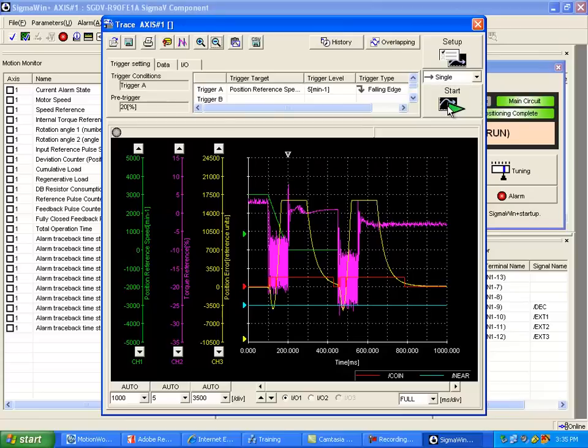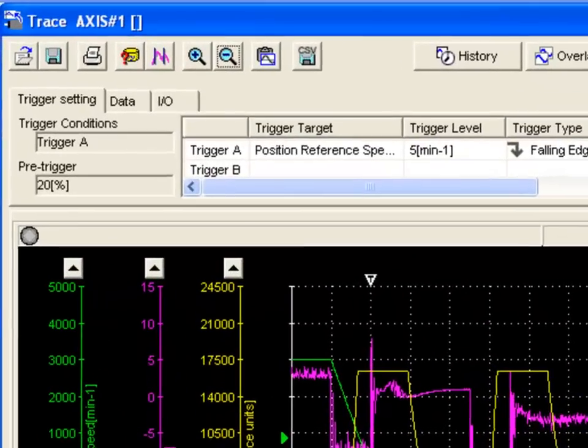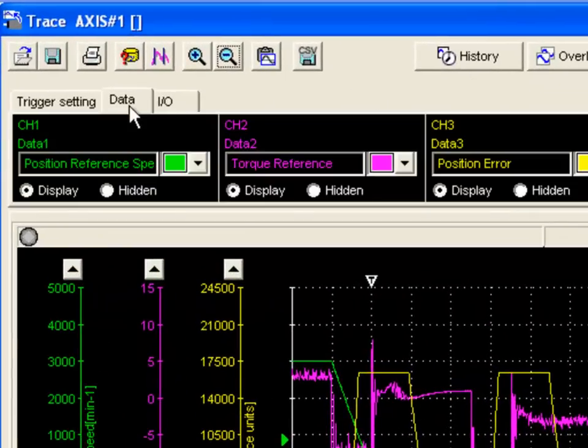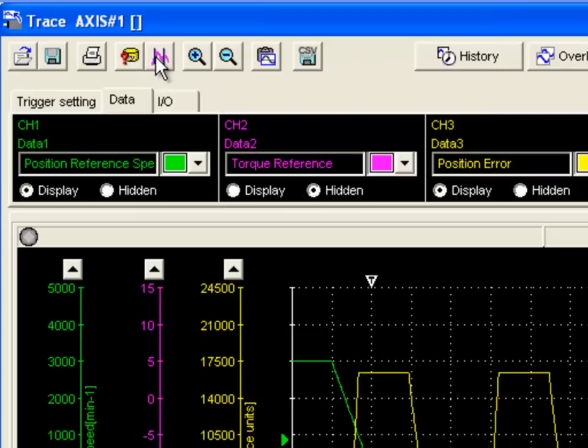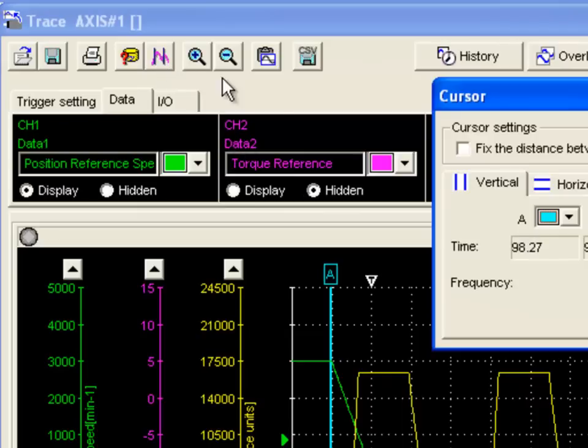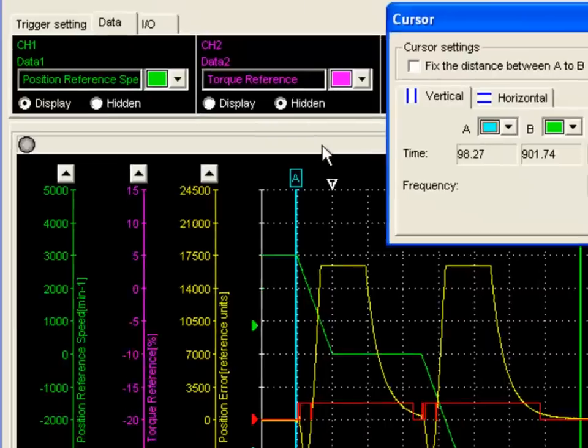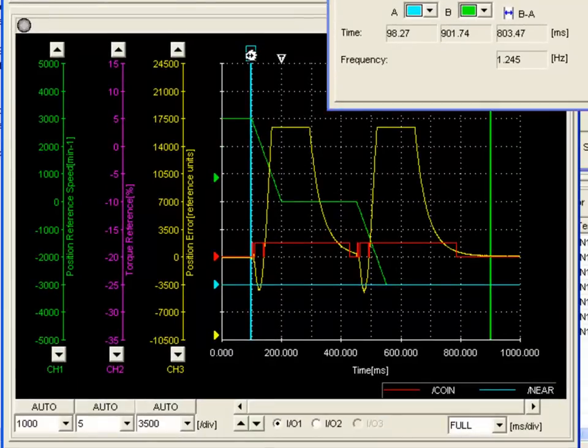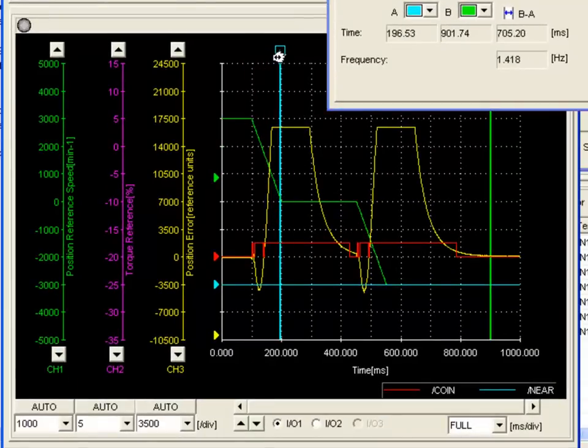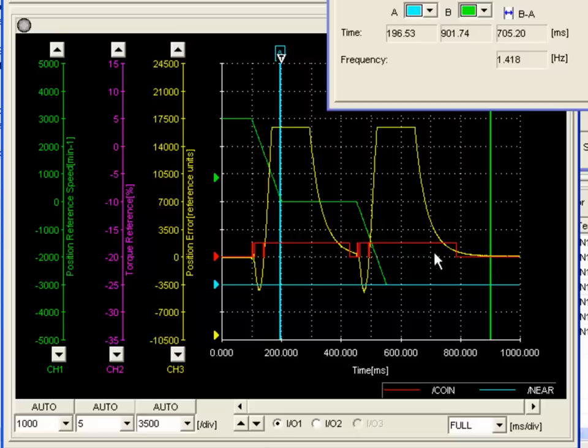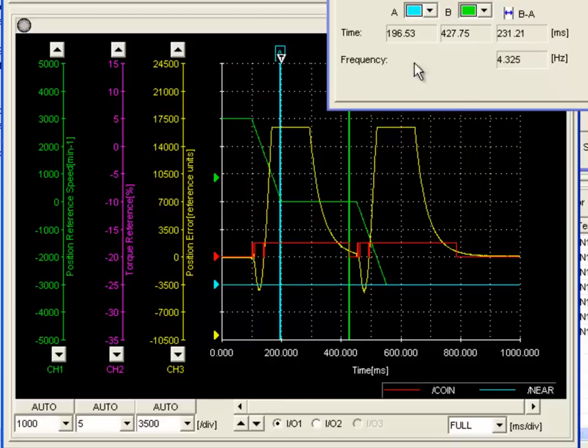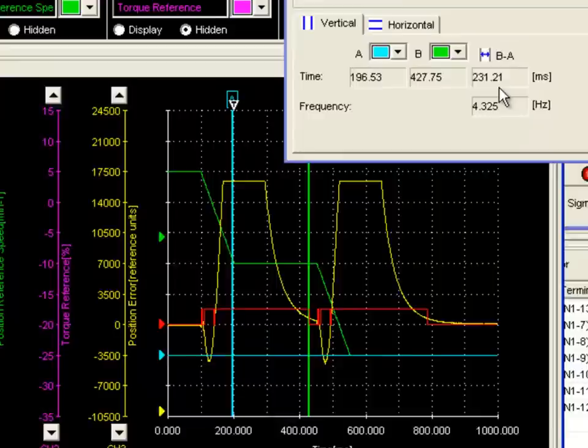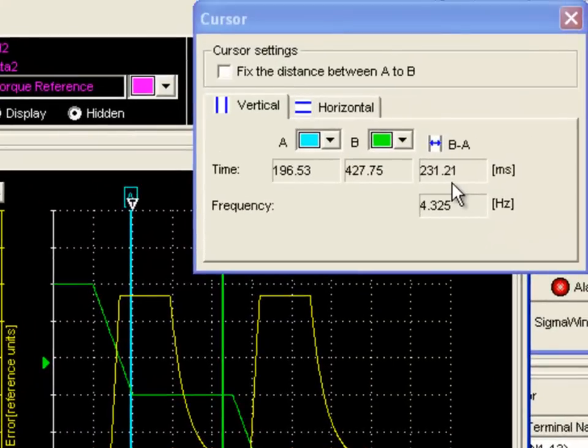Now that we've captured our trace, we want to go ahead to the Data tab on the top. We're going to hide the torque reference to get a better view. Now we need to pull up the cursors. We're going to move the A cursor to the end of the move and the B cursor to the falling edge of the coin signal. In the cursor window, you can see that the settling time is around 231 milliseconds.